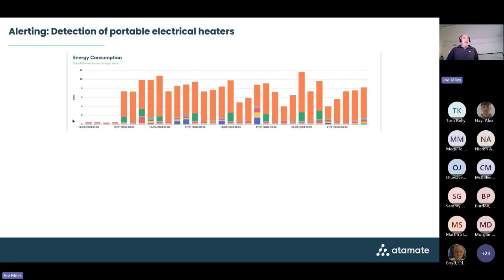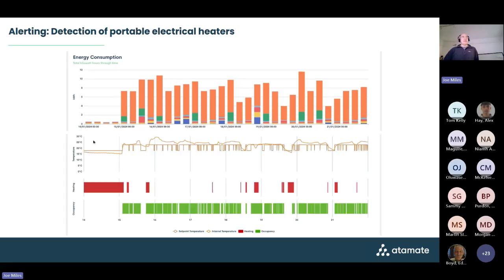And then if we add some monitoring data to that, what these crenellations, the flat lines, are showing is where the temperature should be controlled to. So if the system or the building was working properly, that's where the temperature would be. What we're seeing is the temperature is massively overshooting these lines, and also we can see that the heating's not on. So it's overshooting and it's not on, which is a kind of slam dunk that that space has got portable electric heaters in.